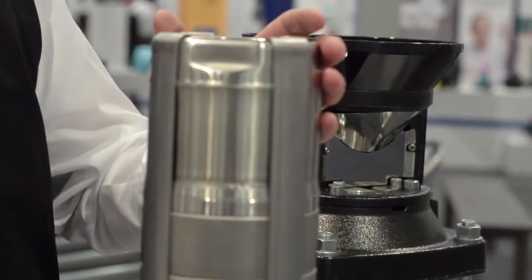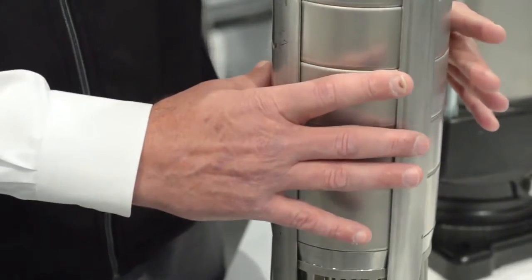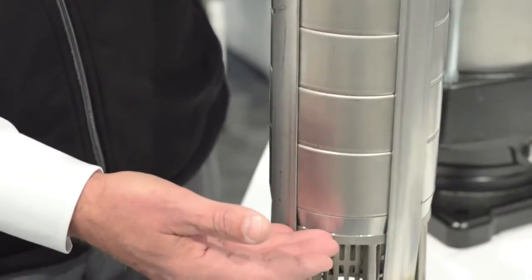Today what we're focused on is what we're referring to as our SSR series. SSR stands for Stainless Steel Strap Design Radial Pump, and basically this is a submersible pump currently available in a 6-inch diameter that you see here — meaning it'll fit inside of a 6-inch well. This is all 304-series stainless steel construction, so highly corrosion-resistant, very heavy-duty components. This has nominal GPM ratings of 100, 150, 250, and 325 gallons per minute, which probably covers the vast majority of hydraulic applications for irrigation as well as municipal and commercial-type work.